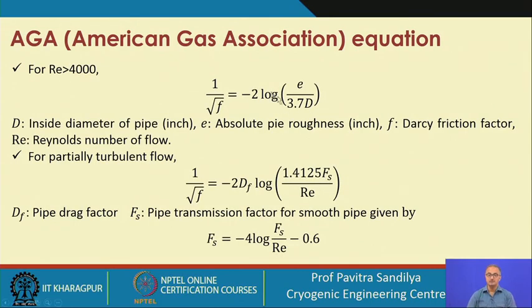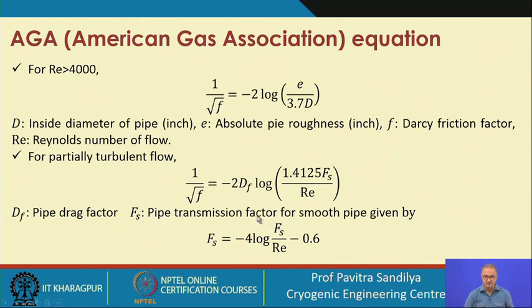For the American Gas Association (AGA), there is another equation. This is given in terms of the friction factor for a rough pipe. For partially turbulent flow, we have this particular expression — all in FPS units. The constants 1.412 and 3.7 arise from this particular unit system. The pipe transmission factor for a smooth pipe is given by F_S, expressed in terms of Reynolds number, and F_S is found in an implicit way.